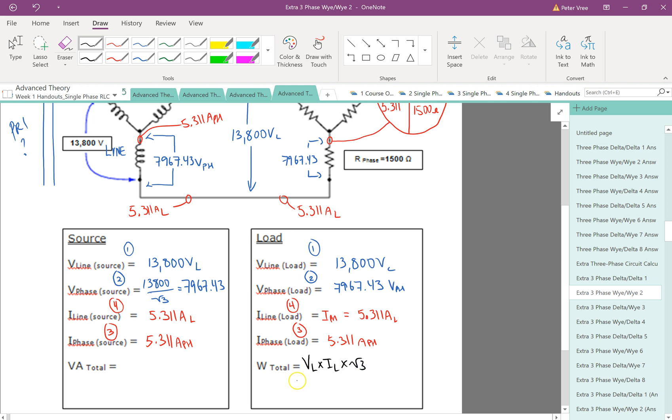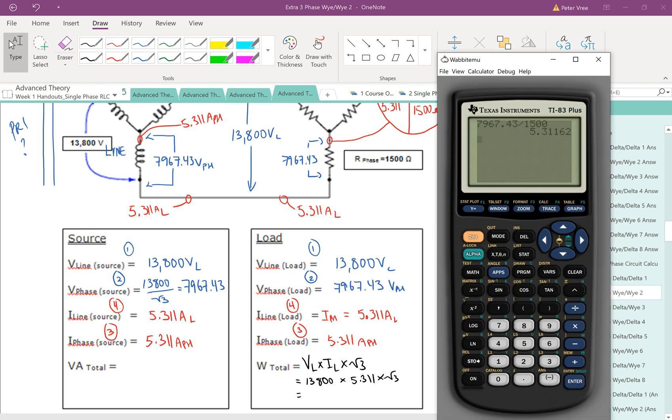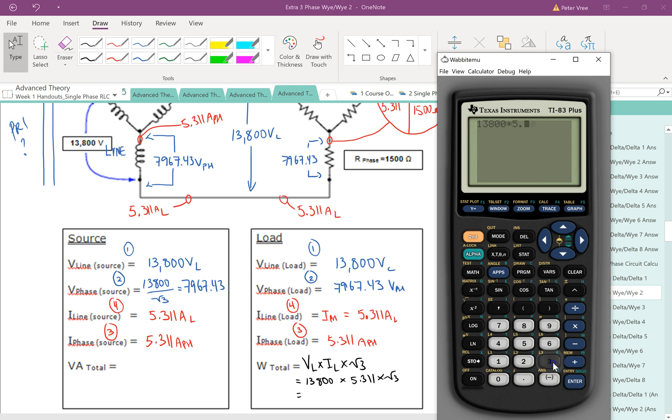And let's see, line voltage is 13.8. Our line current is 5.311. And then we'll multiply it by root 3. And that'll give us the total wattage, which will be identical to the amount of VA. So let's finish that guy off. So we got 13,800. One more zero. Times 5.311. And then we're going to multiply by the square root of 3. And that gives us 126,945.